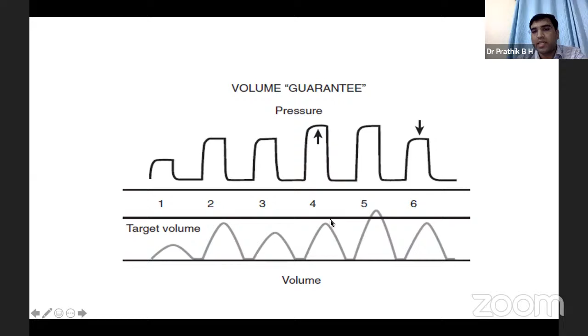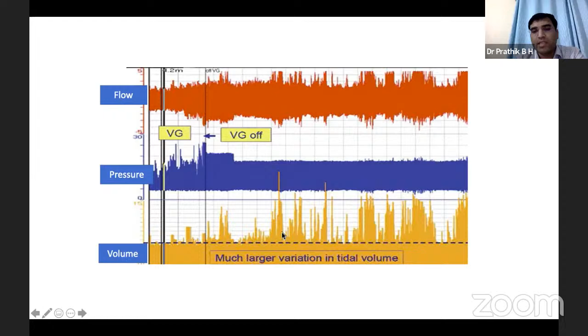You can see in this graph, the first graph is the flow, the second one is the pressure, and the third one is the tidal volume. Here with volume guarantee, there is a lot of fluctuation in the pressure delivery, but the tidal volume delivered when volume guarantee is on is almost constant. Whereas when you switch off the volume guarantee, the pressure delivered is almost constant, but you can see there is so much variation in the tidal volume delivered to the patient.